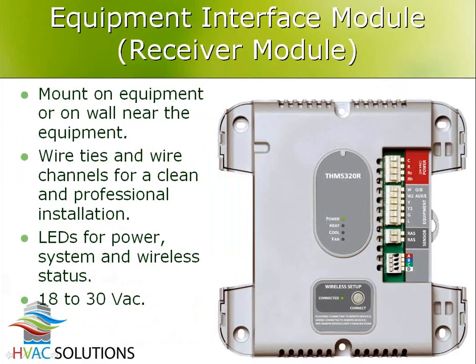So this is what a typical equipment interface module might look like. And as you can see on the right-hand side, you got some basic things, hot and common for power. And if you want to split heating and cooling power, you can do that. You'll see on here, it's for the zoning system, it's 2 stages of heat, 2 stages of cooling, and the fan. And there's also RAS, return air sensor. And that's kind of a backup safety mechanism if for some reason you forgot to change all the batteries in your stats or something like that. Or if you went away for a couple months and your batteries died, and you stop talking between your thermostat and your zones, what would happen is then the system would take over and control based on return air temperature. We'll talk about that in a minute.